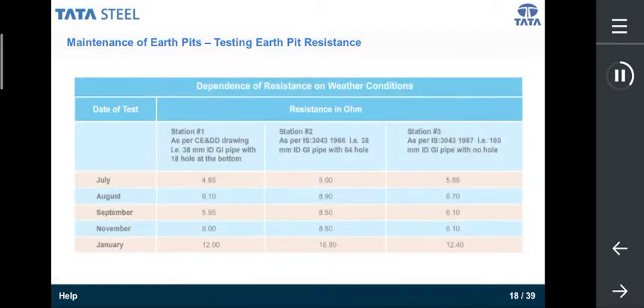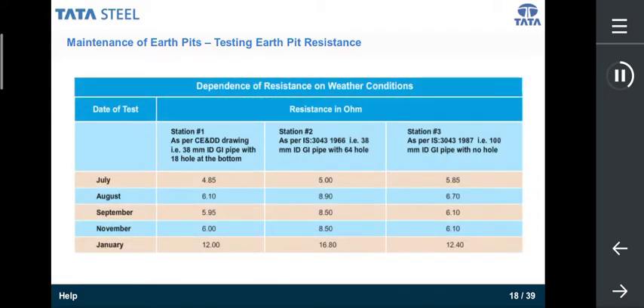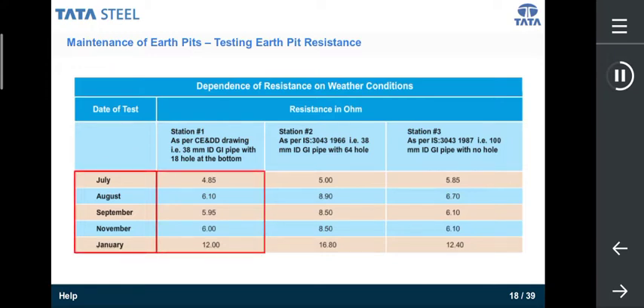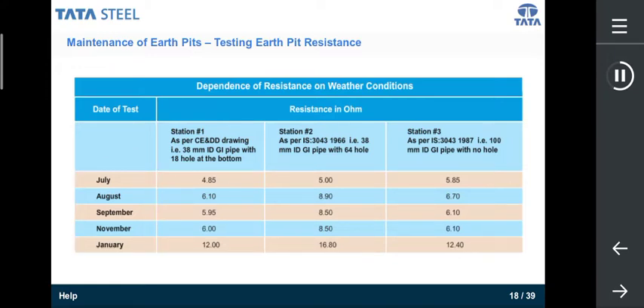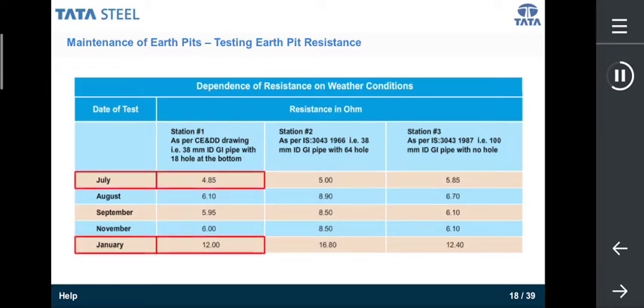In this context, it is important to have a look at this table. The table here conveys how the resistance of the earthing pit varies depending upon the seasonal condition. For example, if you take a look, the value of each month differs. While there is a lower value in July, January has a higher value. Therefore, you can see that the resistance values vary with the season.